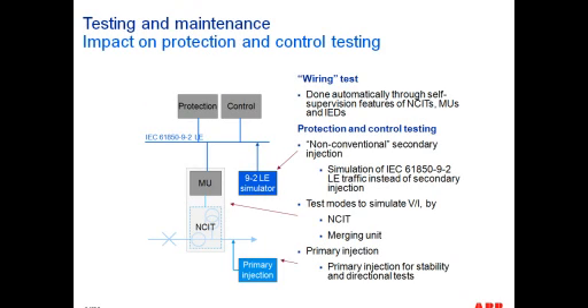And then let's talk real quick about the impact of these types of systems on protection and control testing. So we're used to using test switches to isolate the relay with your instrument transformers, with VTs, CTs, as well as all the different control signals, whether it's inputs onto the relay or outputs from the relay onto the rest of the system. So now if you have a device that takes sample values input onto your relay, how do you go ahead and test for that?